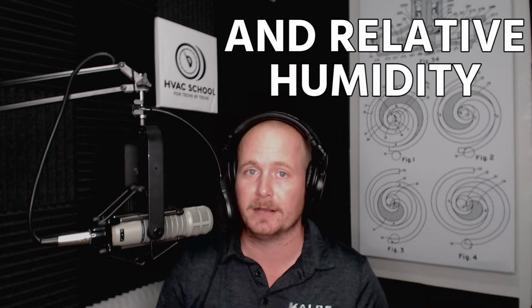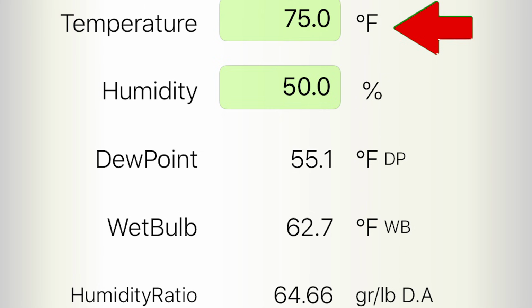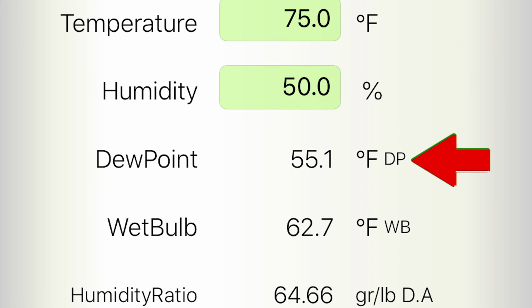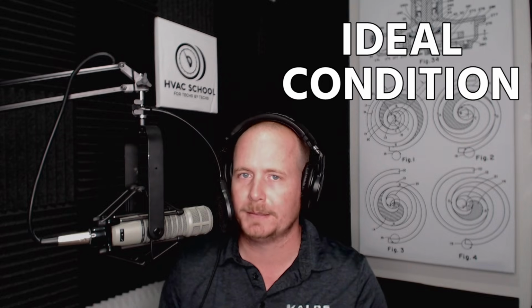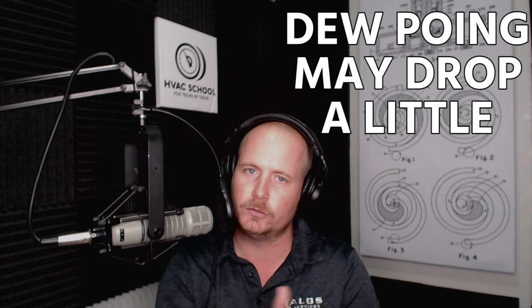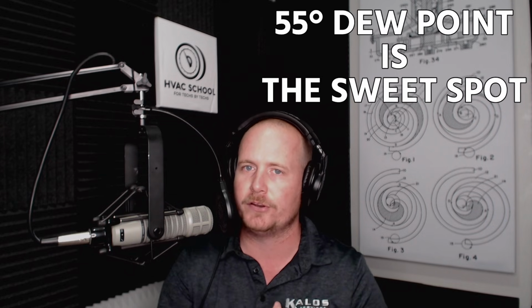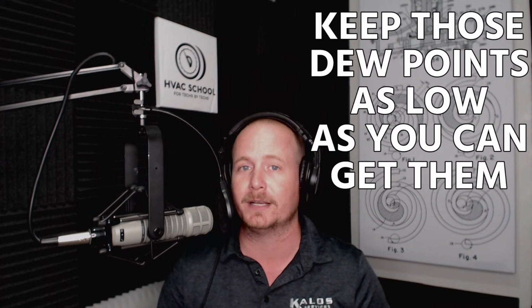By controlling dew point inside the conditioned space and the relative humidity, generally in cooling mode, 75 degrees at 50% relative humidity, which equals a 55 dew point, that's sort of the ideal condition for most people. Sometimes they want it a little cooler than that so that dew point may drop a little bit, but that 55 degree dew point is kind of a sweet spot. When you get into attics, that's often unrealistic. If you condition them with dehumidification such as the SD12, you can often get to that level.